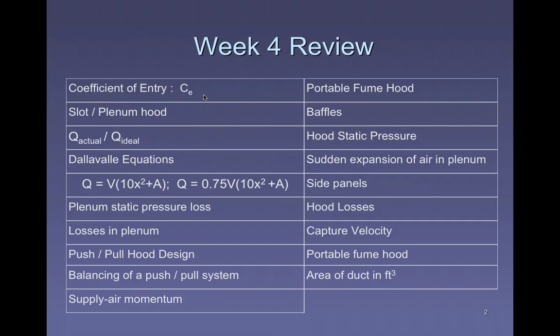The coefficient of entry is really an efficiency measurement, right? It's equal to the square root of the velocity pressure divided by the positive value of the static pressure. Let's think about this. If the velocity pressure is equal to the static pressure, that means that the velocity pressure and the static pressure are the same. It's basically, that means that there's no resistance. 1/1, the square root of that is 1. It's 100% efficient, right?